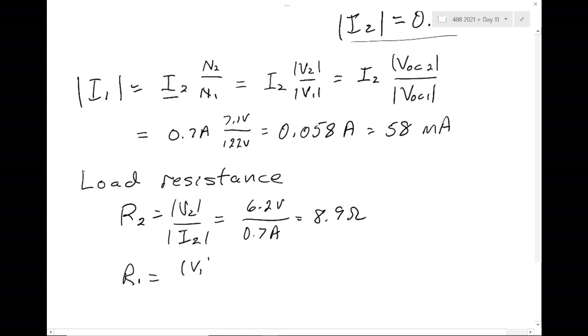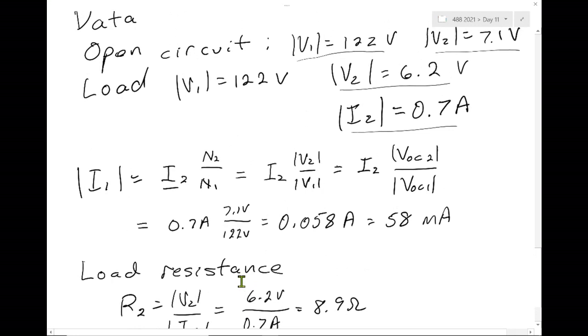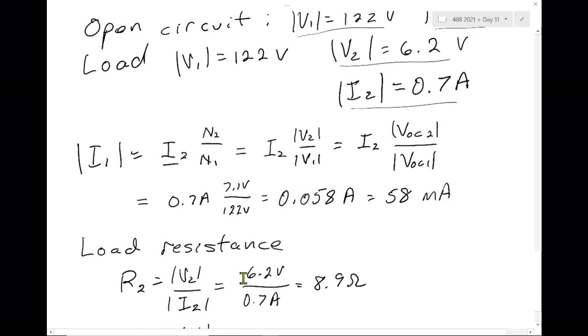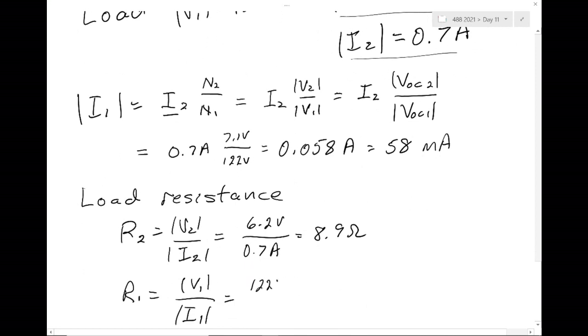R1 is equal to V1 under load over I1 under load. V1 I measured, and V1 under load was 122 volts. I1 under load I calculated as 0.058 amps. And when I do the calculation on that, I'm going to see that I have a much higher resistance appearing on the primary. It's not really there. It's connected on the secondary. 2100 ohms.